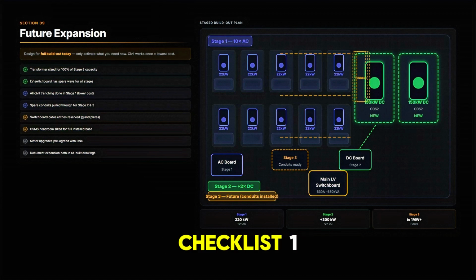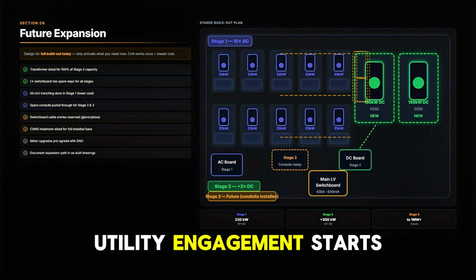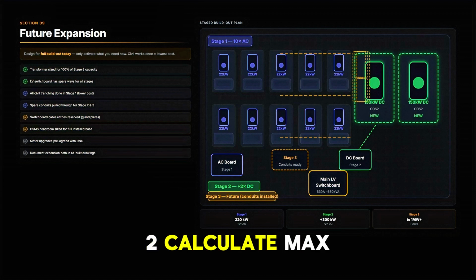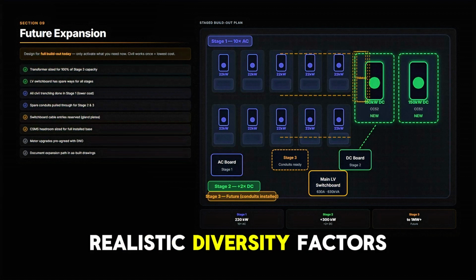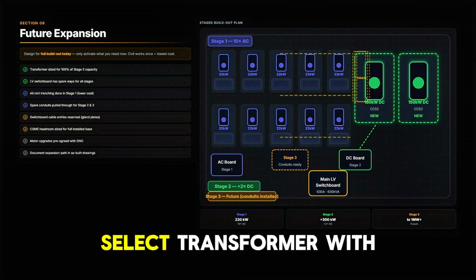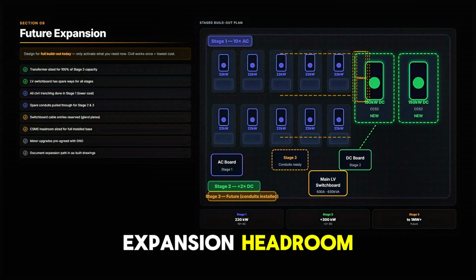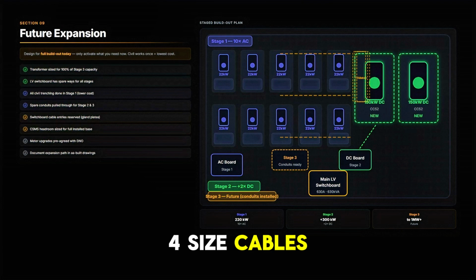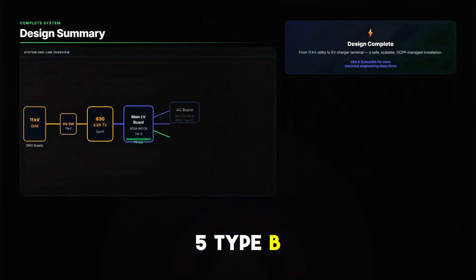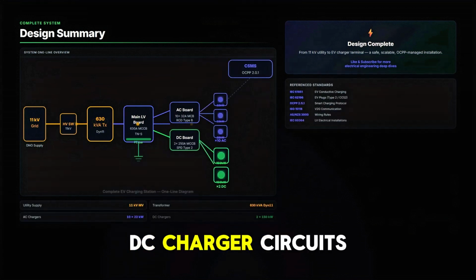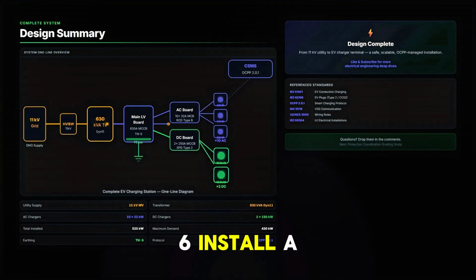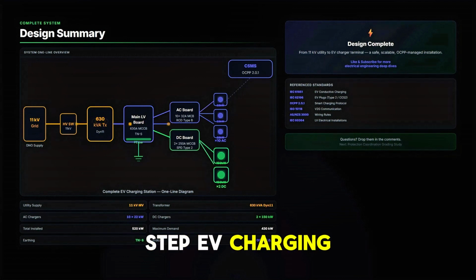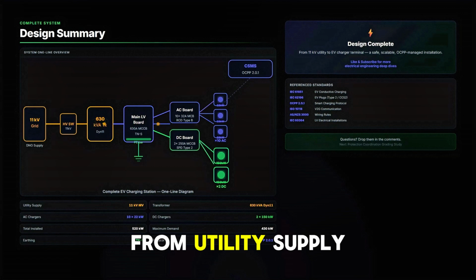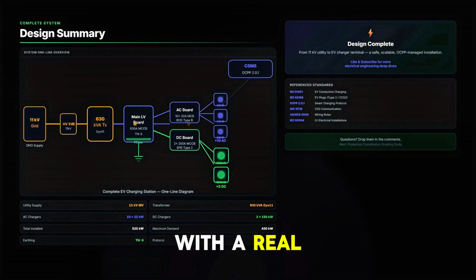8-point design checklist. 1. Utility engagement starts on day 1. 2. Calculate maximum demand with realistic diversity factors. 3. Select transformer with expansion headroom. 4. Size cables for the worst case of 3 criteria. 5. Type B RCDs on all DC charger circuits. 6. Install a compliant load management. That is the complete step-by-step EV charging station design, from utility supply to charger terminal, with a real worked example at commercial scale.